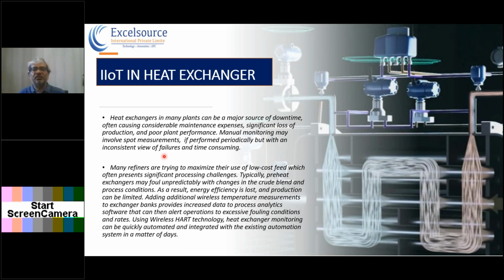So, IoT in heat exchangers. We have demonstrated earlier in our presentations that the pinch technique is used, and even without the pinch technique, if there are heat exchangers where heating and cooling is done, how is IoT going to help us with this particular heat exchanger? We have to see that the profile of the heat exchanger is maintained as designed. If it is not maintained, then we may end up losing heat and utilizing more energy, or more water in cooling applications, or more steam in heating applications.